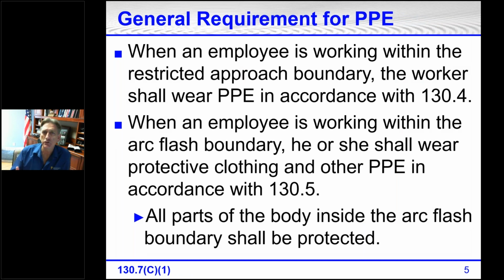Okay, so these are the two places in 70E where we're going to look for the requirements for both shock and arc flash. When an employee is working within the restricted approach boundary, the worker has to wear PPE in accordance with 130.4. The requirements for shock are in 130.4. When an employee is working within the arc flash boundary, he or she has to wear protective clothing and other PPE in accordance with 130.5. It also goes on to say all parts of the body inside the arc flash boundary have to be protected.